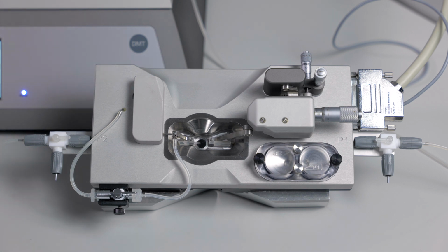Be careful when moving your chamber around. If you bump the metal ports on the three-way valves, you can break the internal seal and cause a pressure leak. If you have a broken or clogged cannula, you will need to replace it. The process for changing the cannulas does change depending on the side.